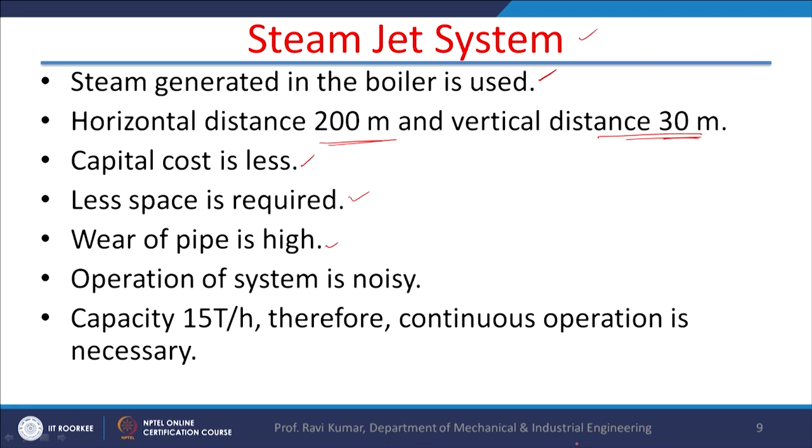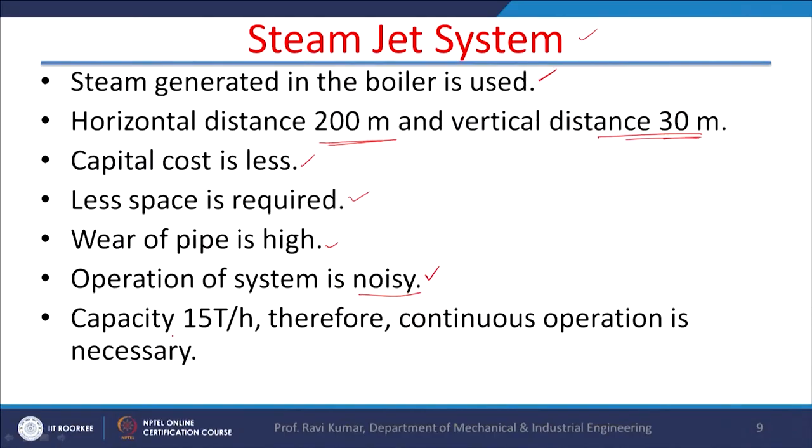The operation of the steam jet system is noisy. Wherever high velocity gases are dealt with, noise is a big issue. This is true not only in power plants but in any plant — if air velocity is high, noise becomes a major limiting factor for any pipe or duct. The capacity of the steam jet system is 15 tons per hour and it has to be continuously in operation.